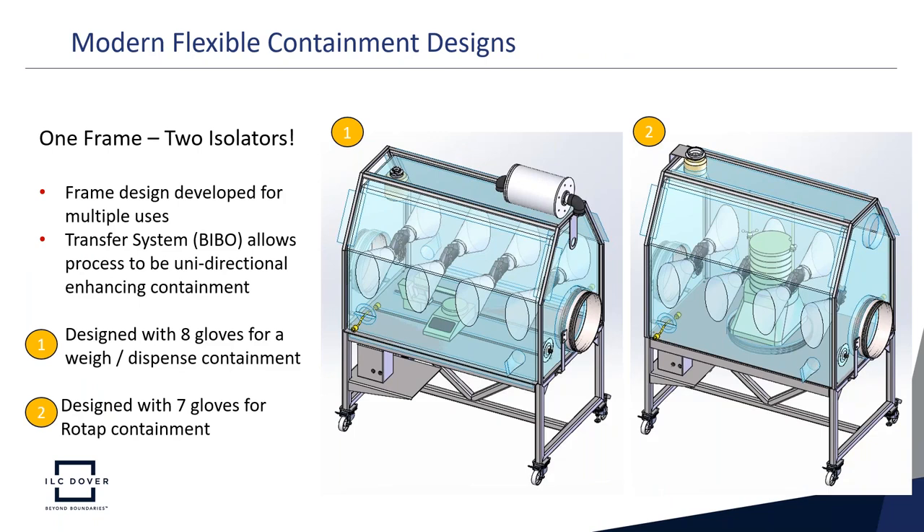Here's an example of one frame supporting two isolators. The exact same frame is used for two different processes simply by changing the flexible film isolator. The frame design is developed for multiple uses, and the bag-in, bag-out transfer systems allow processes to be unidirectional, enhancing containment — products pass in from one side and out the other. Isolator one has eight gloves for a weigh-and-dispense application; isolator two has seven gloves with a Rotap system inside for containment during the Rotap process. One frame, two completely different designs.